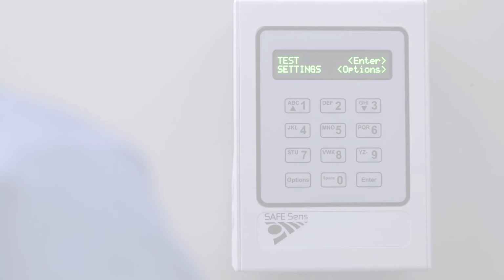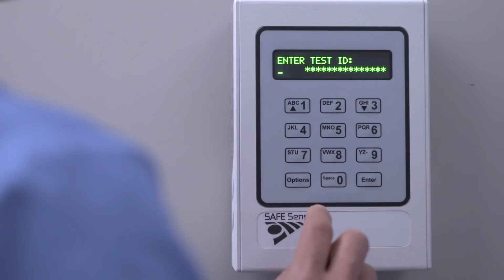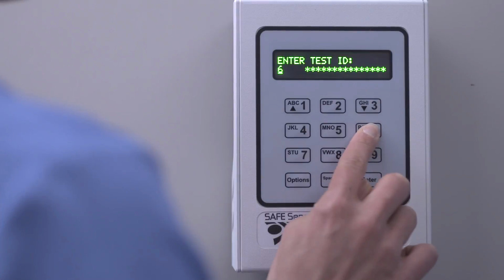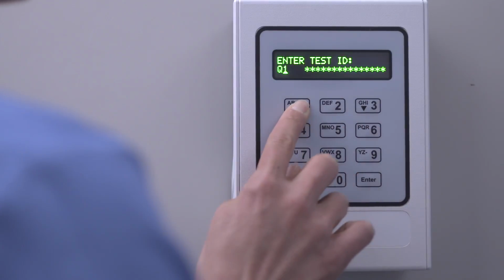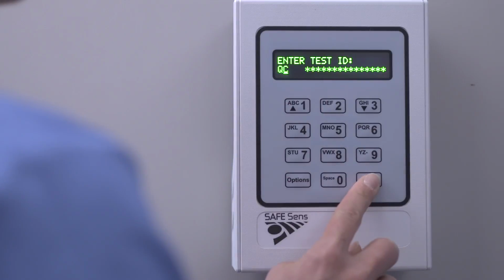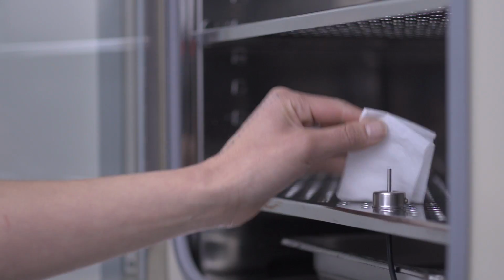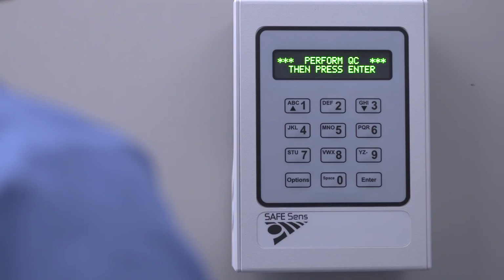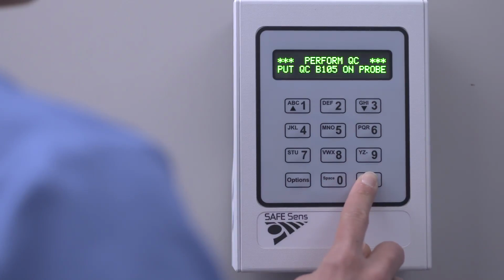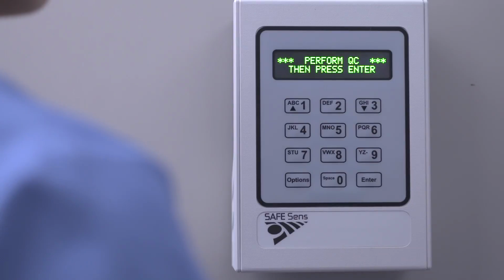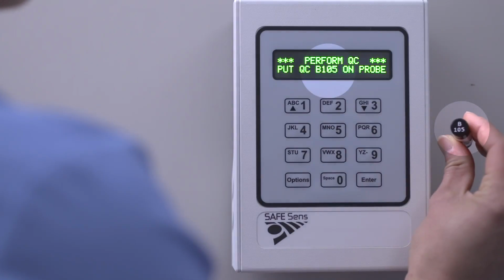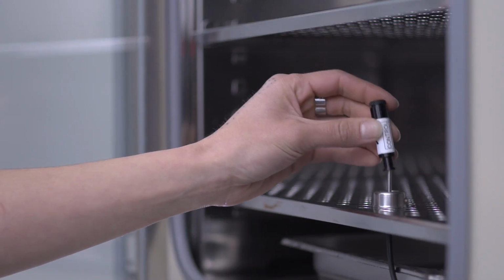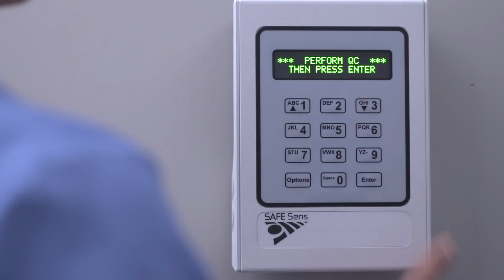We will first run a QC test on the SafeSense reader to ensure it is functioning correctly. From the home screen, press Enter, type in QC, and press Enter. The fiber probe is cleaned with a dry tissue like a Kimwipe to remove anything that blocks the optical path. Then press Enter on the SafeSense and match the serial number of the QC standard against the number on the screen. Place the standard on the fiber probe and press Enter.